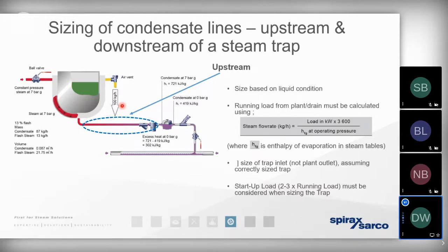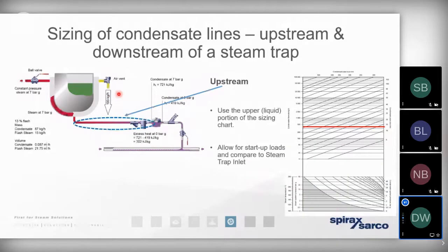If we hadn't done that, then that warming up load that was present when we were warming the system up from cold would result in the condensate backing up and starting to flood the process. And remember, condensate has significantly less heat energy contained within it than steam does. So that would result in a little bit of water hammer as the steam pressurized the condensate, but it would result in a significant slowdown in bringing the process up to the required temperature in the desired design conditions. So when we're looking at removing the condensate, that liquid, upstream of the steam trap, yes, it's a liquid. Yes, it exists at a high temperature because of the pressure. But by referring back to the steam tables, we also understand that there's a significant amount of sensible heat present in that high temperature, high pressure condensate. But because it's under pressure, it is a single phase liquid.